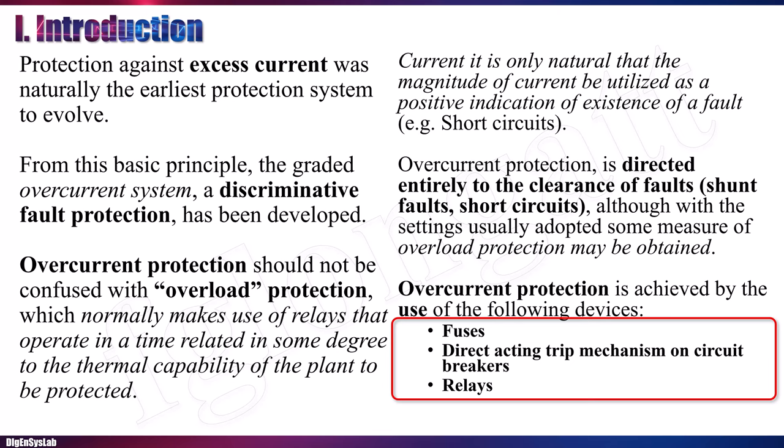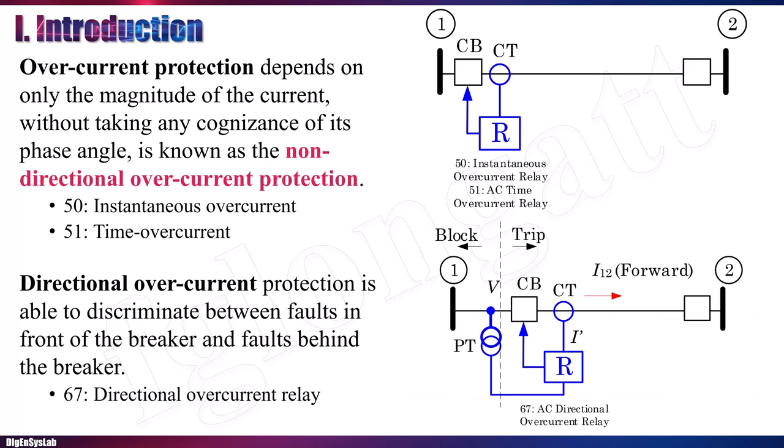There are several overcurrent protection devices in electrical power systems. The oldest and most famous is the fuse. Others include the direct acting trip mechanism on circuit breakers, used in low voltage systems, and relays at distribution level that create the trip signal to the circuit breaker. If we consider the magnitude of the overcurrent, we can define a protection mechanism called non-directional overcurrent, based on the magnitude of the current as the main indicator to differentiate normal from abnormal conditions.